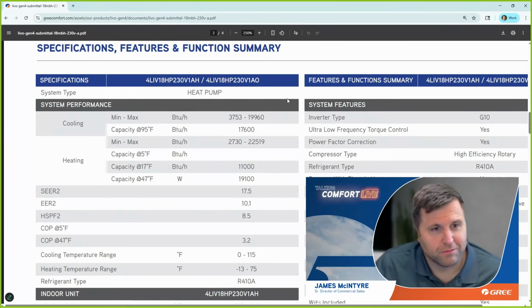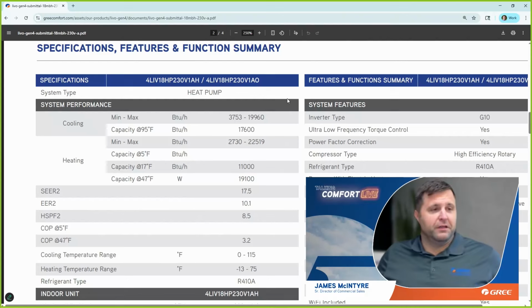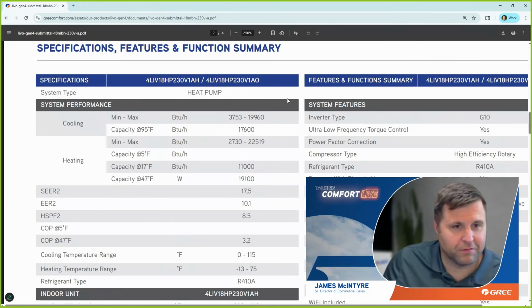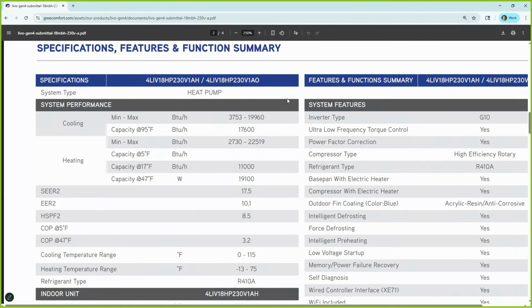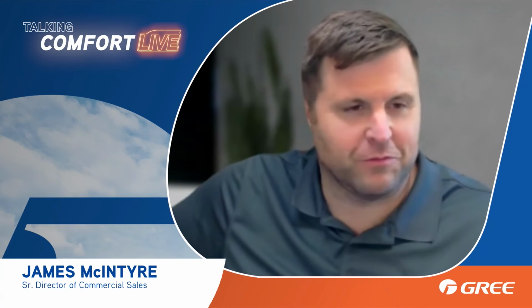Does it make sense? I think that's pretty evident. At that point, yes, it's too large. You know, the thing is, if I took a 1.5 ton regular system and put it in the same situation, oh, your walls would be dripping. You would never be able to remove the humidity in that space.